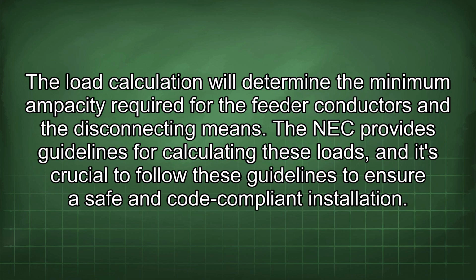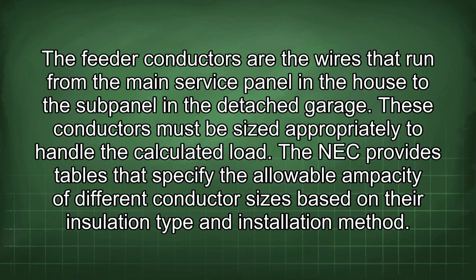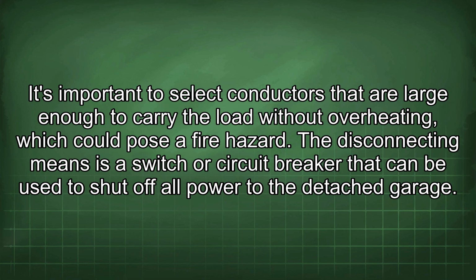The feeder conductors are the wires that run from the main service panel in the house to the subpanel in the detached garage. These conductors must be sized appropriately to handle the calculated load. The NEC provides tables that specify the allowable ampacity of different conductor sizes based on their insulation type and installation method. It's important to select conductors that are large enough to carry the load without overheating, which could pose a fire hazard.